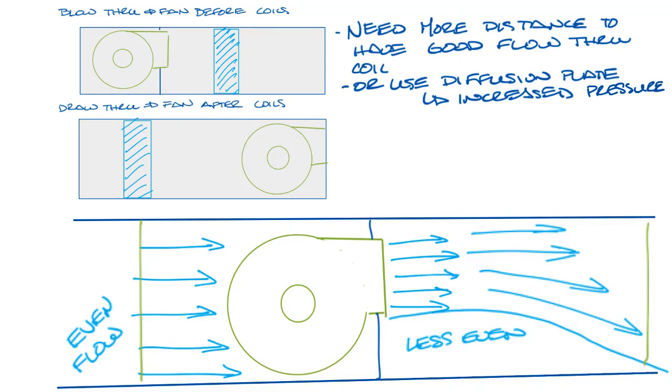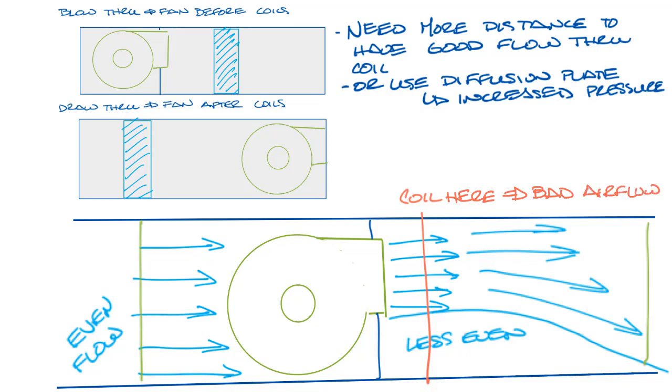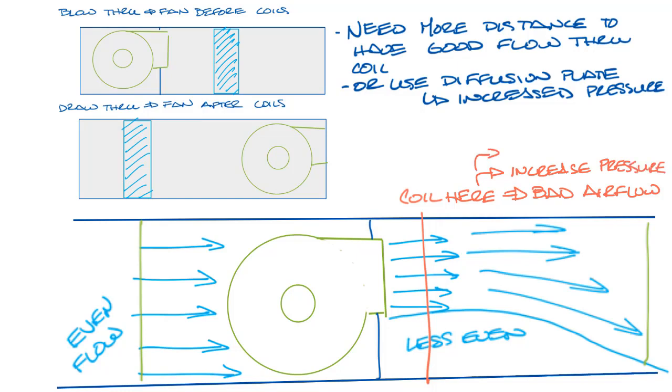Now if you put the coil here, close to the fan discharge, you could have too much face velocity at the area where the air hits the water coil, and this is going to reduce the capacity of the coil, because you're not using the air around the outside. It will also increase pressure drop.